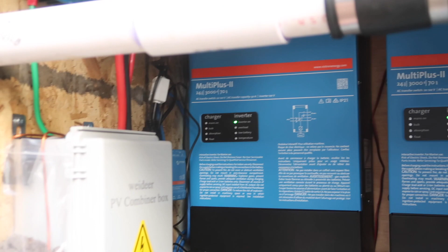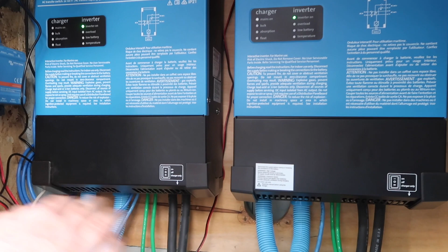We'll continue talking about the AC distribution side of things first. Power comes from that big master 50 amp breaker for the shore power, and gets appropriately split up into neutrals, earths, and a hot leg for each of these inverters. These are called MultiPlus-II. They do have the capability to pass the second leg through them, but we're not using that feature - we're simply feeding one leg of 120 volts into this one and one leg of 120 volts into this one.